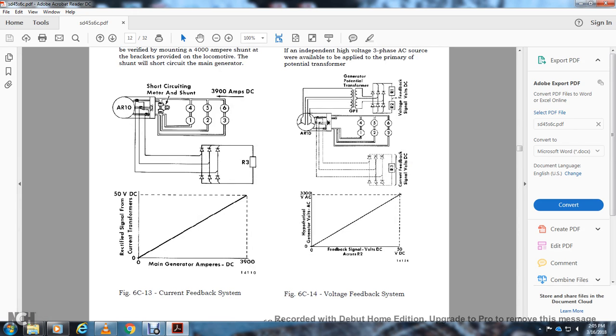Figure 6C-13 shows the current feedback system. The main generator amperes run from 0 to 3900, running at a slope, making the equation y equals mx, or 39 over 50 volts. The slope of the line makes it, let's say, 1 in 50. So your y equals mx plus b would be between the 50 volt rectifier signal and the current transformer, the main generator amps to DC, 3900, and voltage show the short circuiting metering shunt of the 1, 2, 3, 4, 5, and 6.